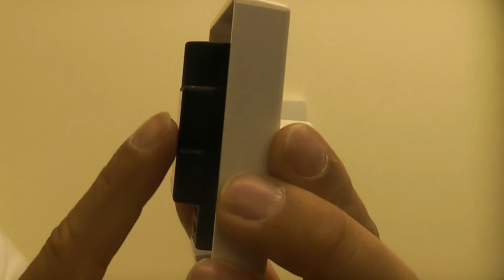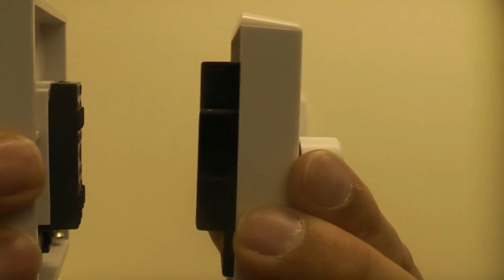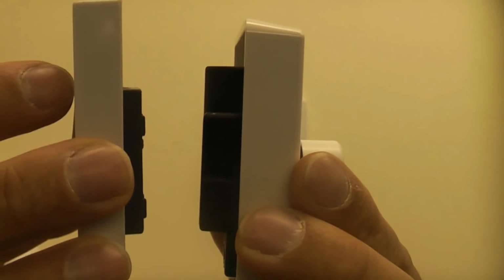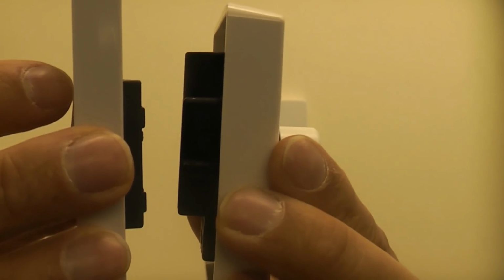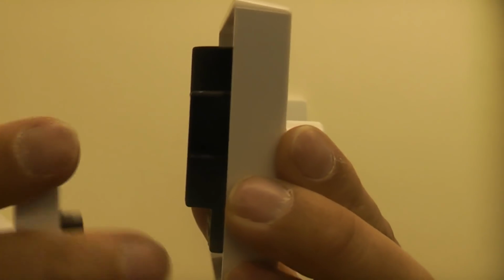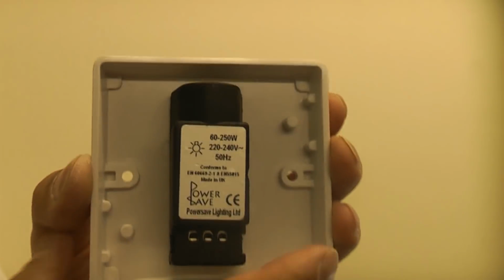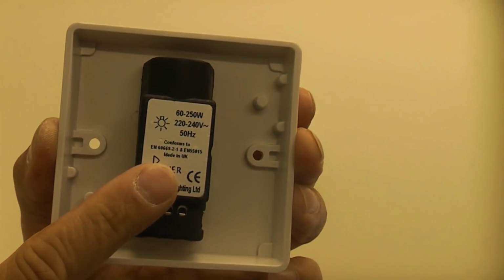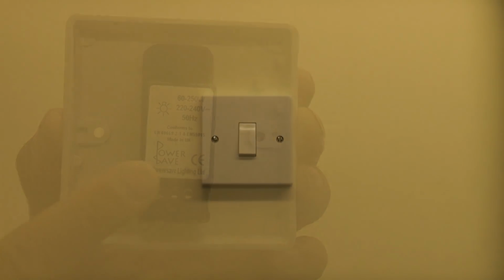Before you install a dimmer, you need to check that your back box is deep enough to accommodate the actual thickness of the dimmer. These are a couple of millimeters thicker than an actual switch. You can see the switch there compared to that, and that probably sticks out another 10 millimeters more than what the single switch does. So you have to be careful and ensure that the back box is deep enough to accommodate the dimmer.